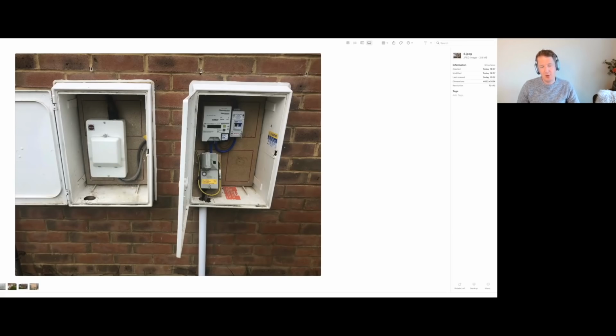Now, the reason for installing this is because the supply cable from the meter to the main house consumer unit is more than 3 meters. You're only allowed 3 meters of these cables, which we call the main tails, off the main fuse. If it's longer than that, you need to run it differently, and you need to install a switch fuse, which is what they've done. They've installed this switch fuse. Maybe it's a 63 amp or 80 amp or 100 amp switch fuse, and then they've run an armored cable from there to the consumer unit in the house.